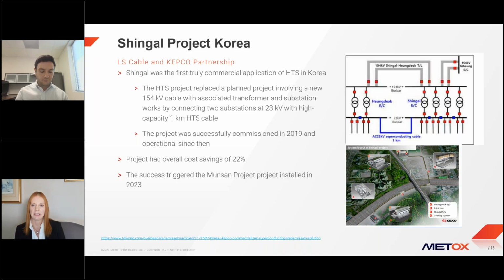We're looking at a network that's 154 kV transmission and a 23 kV distribution network. The need was to bring additional supply into the Shingal station from the Hongdeok station. The original plan was to add a third 154 kV cable and additional transformer capacity at Shingal, but the right-of-way between the stations and the substation space at Shingal were extremely constrained, so they couldn't do the project that way. That's how they ended up looking at the high-temperature superconductor application — instead they installed a 23 kV cable, the same cable Jay showed a picture of earlier.